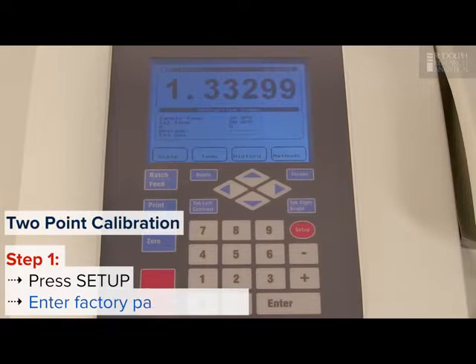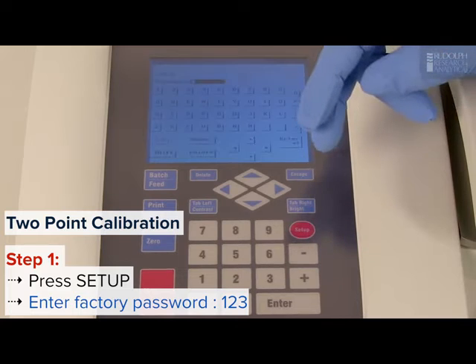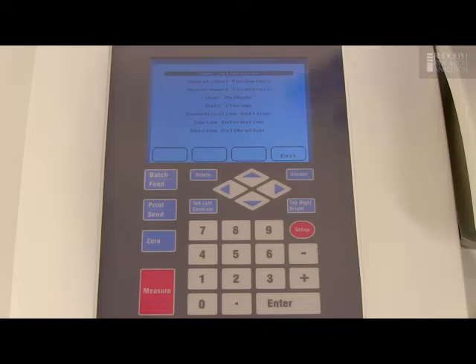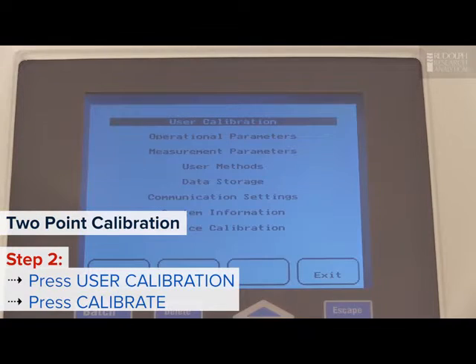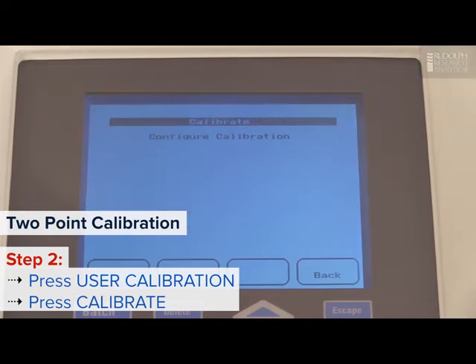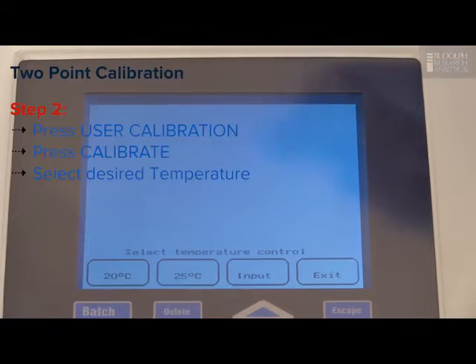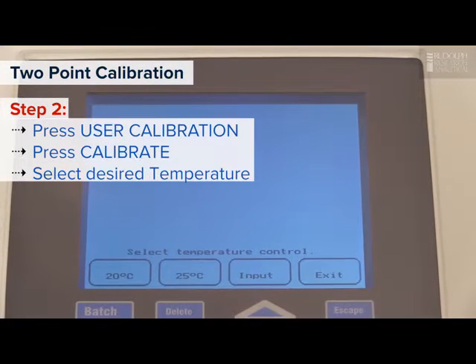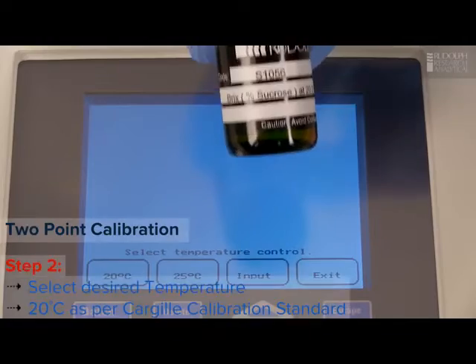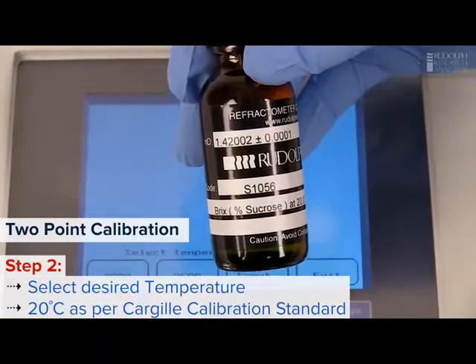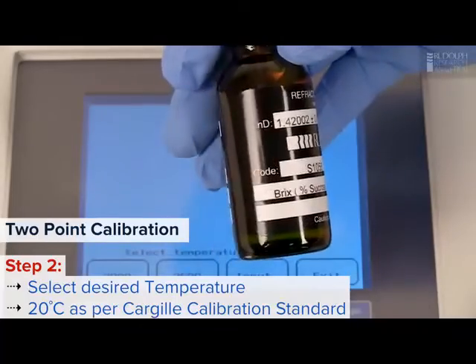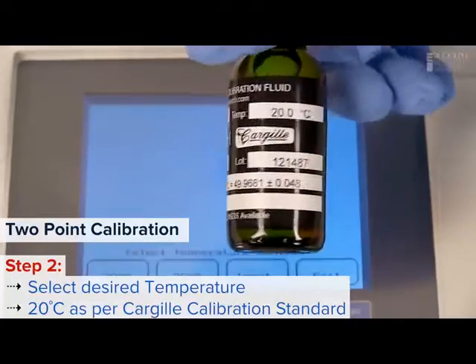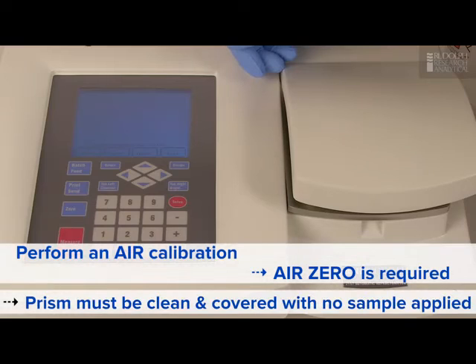To perform a 2-point calibration, you have to go into the setup menu. You press setup and the default factory password is 123 enter. The first option you see is user calibration. You hit calibrate and you select the desired temperature you're going to be performing the calibration. In this case, we're going to be using 20C because that is the value of the calibration standard that we're using. The first step of the calibration is for the instrument to perform an air calibration.